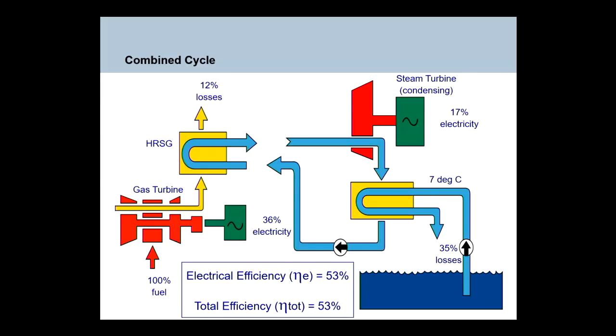Okay, we'll see a slide in a minute. Typically, 53% is a small combined cycle unit. Big modern units can get up to 63% or thereabouts. So a much better efficiency than open cycle, but the capital costs of the plant are much higher.